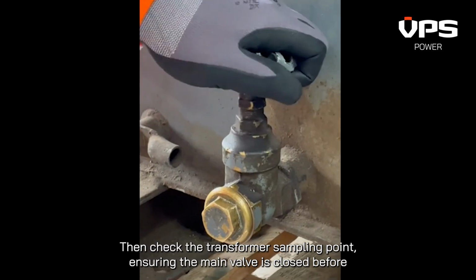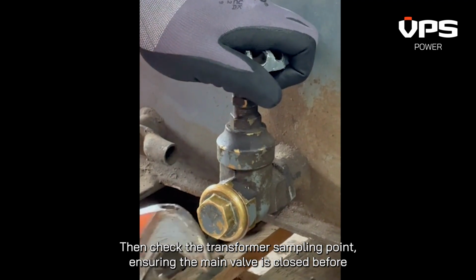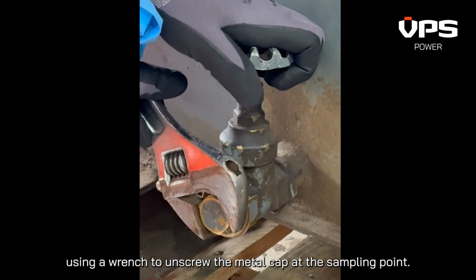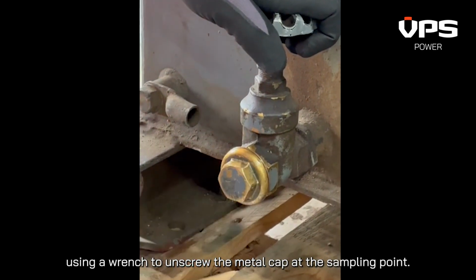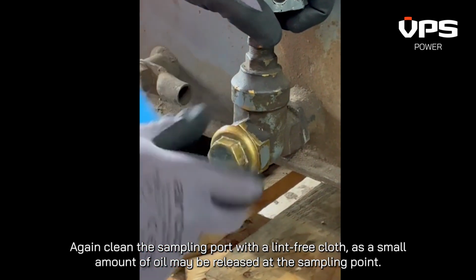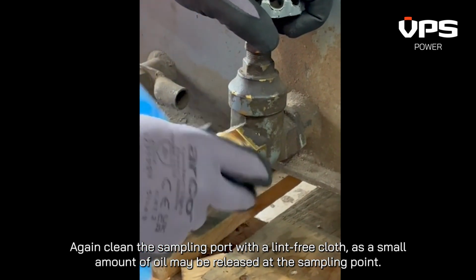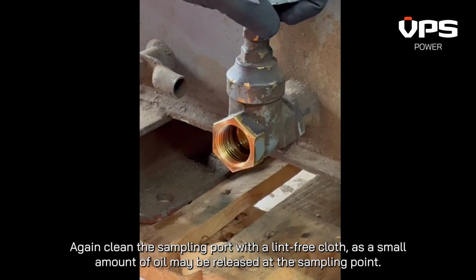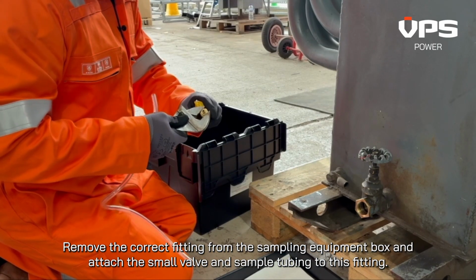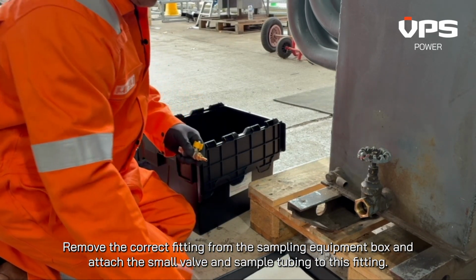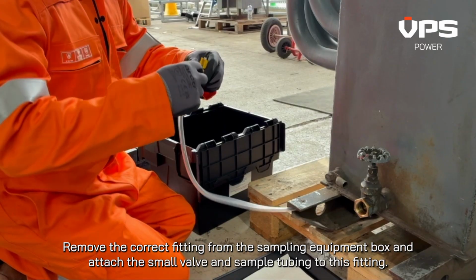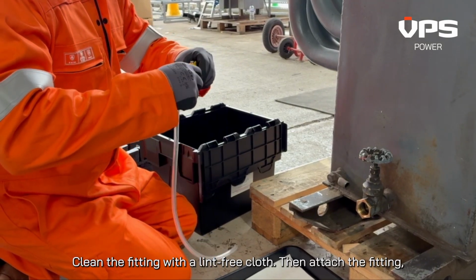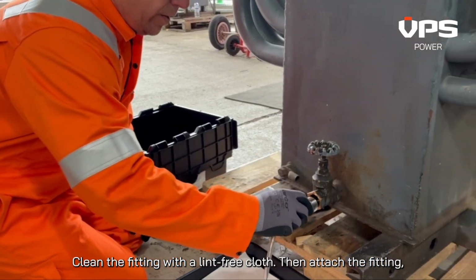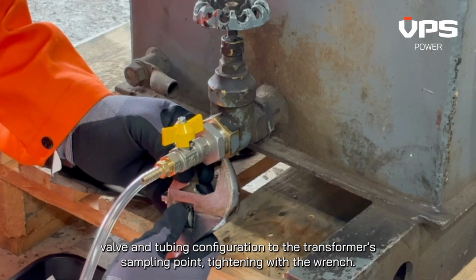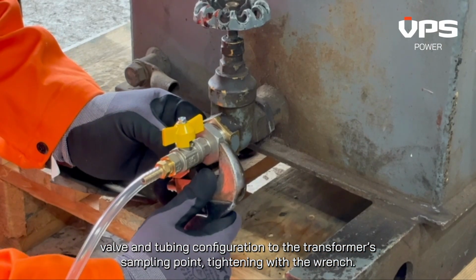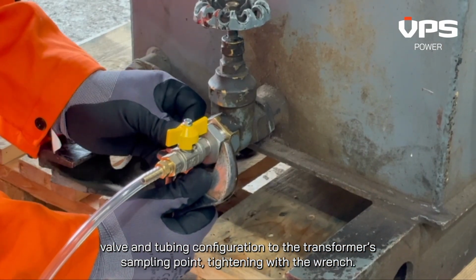Then check the transformer sampling point, ensuring the main valve is closed before using a wrench to unscrew the metal cap at the sampling point. Again, clean the sampling port with a lint-free cloth, as a small amount of oil may be released at the sampling point. Remove the correct fitting from the sampling equipment box and attach the small valve and sample tubing to this fitting. Clean the fitting with a lint-free cloth. Then attach the fitting, valve and tubing configuration to the transformer sampling point, tightening with the wrench.